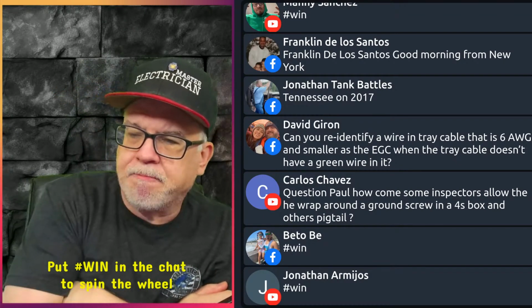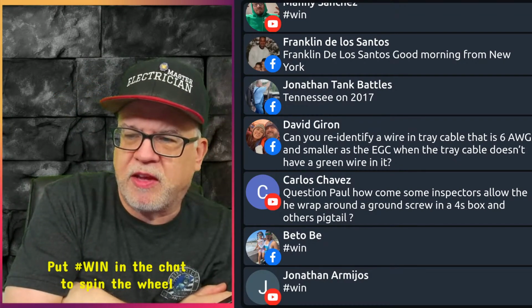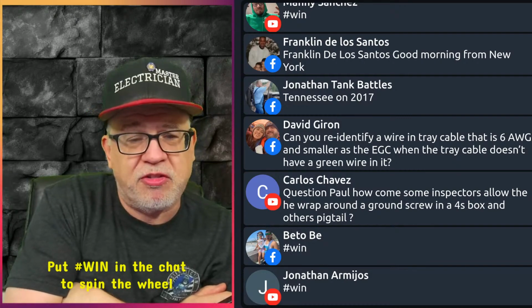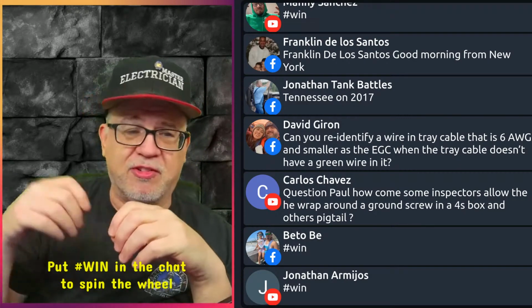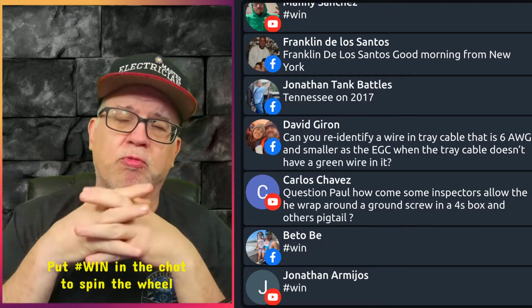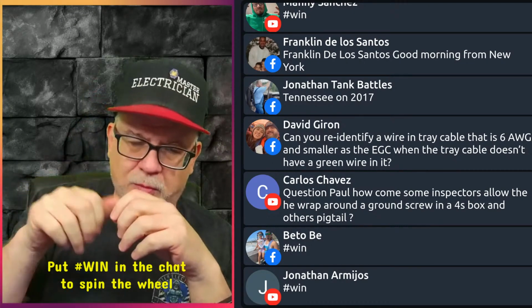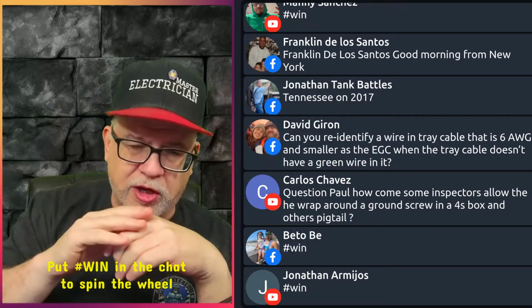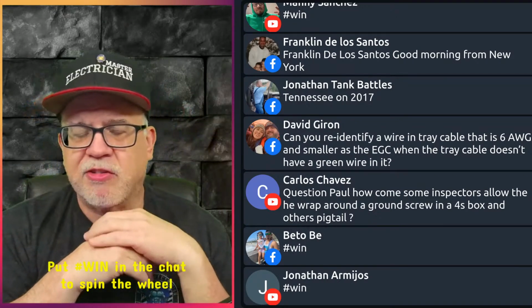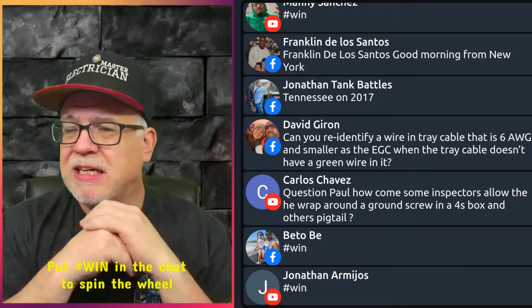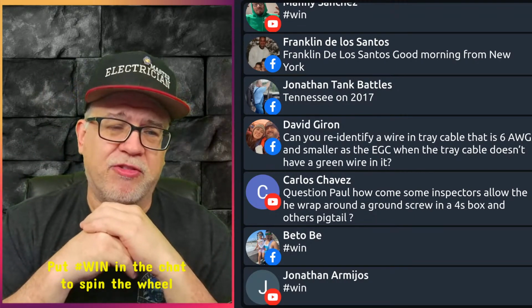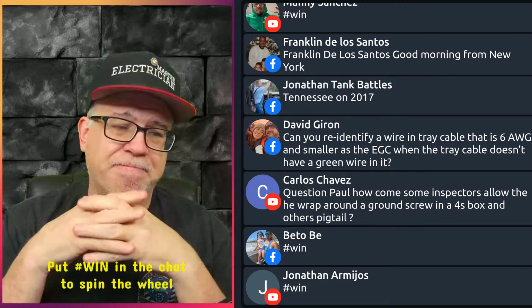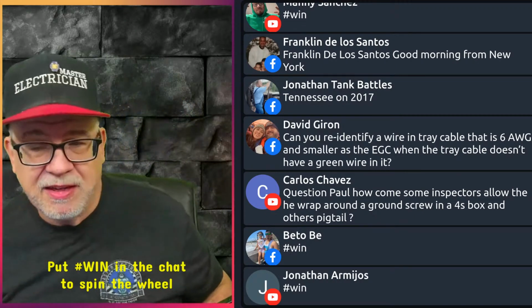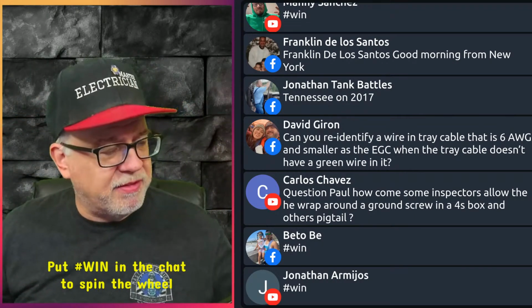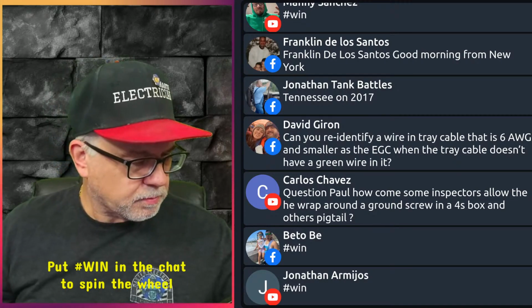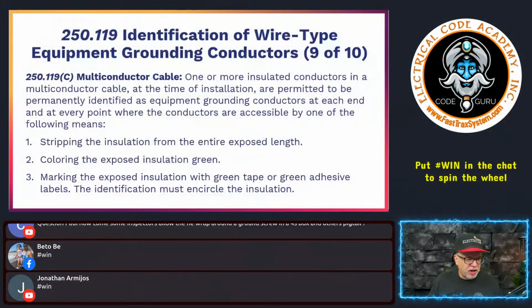So at the end of the day, the reason I would say don't go with the method of stripping off the insulation is, one, it's not just going to slide off. You have to take it off in pieces, and you run the risk of damaging the equipment ground. The more you try to cut insulation off, the more chances you could nick up the copper. So I'd much rather you just re-identify it at its termination with green tape, that type of thing. Probably the best advice I can give you: don't mess up that equipment ground. And that should have answered the other questions we had.